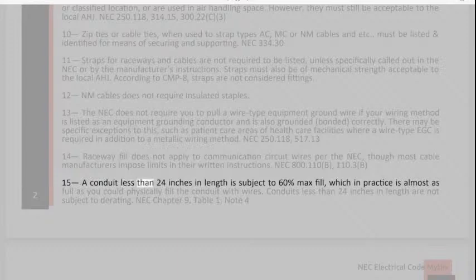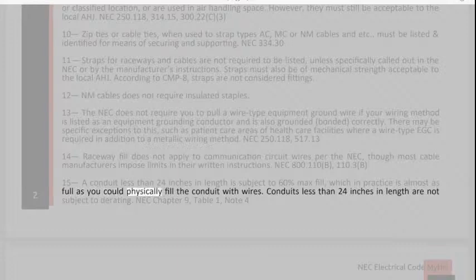15. A conduit less than 24 inches in length is subject to 60% max fill, which in practice is almost as full as you could physically fill the conduit with wires. Conduits less than 24 inches in length are not subject to derating. NEC Chapter 9, Table 1, Note 4.